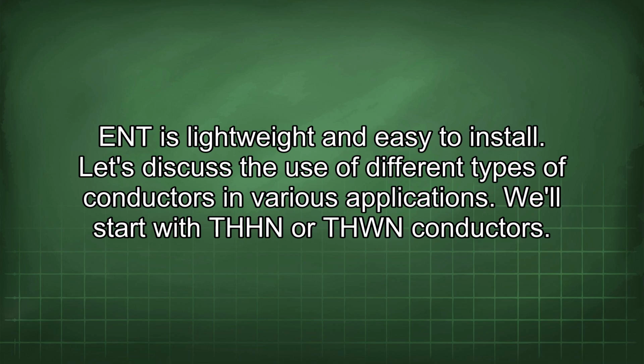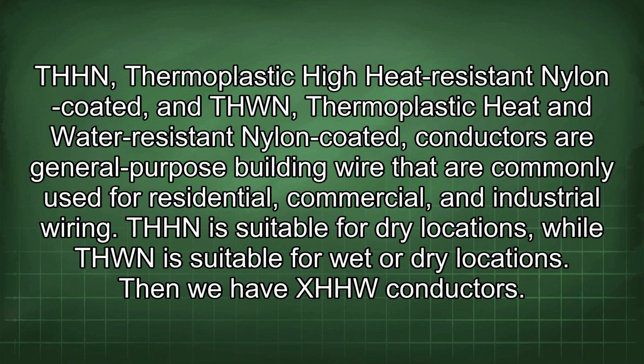We'll start with THHN or THWN conductors. THHN, thermoplastic high heat-resistant nylon coated, and THWN, thermoplastic heat and water-resistant nylon coated conductors, are general purpose building wire that are commonly used for residential, commercial, and industrial wiring. THHN is suitable for dry locations, while THWN is suitable for wet or dry locations.